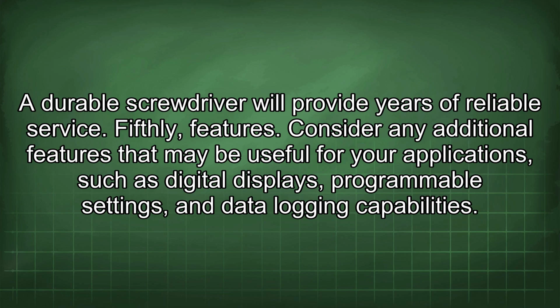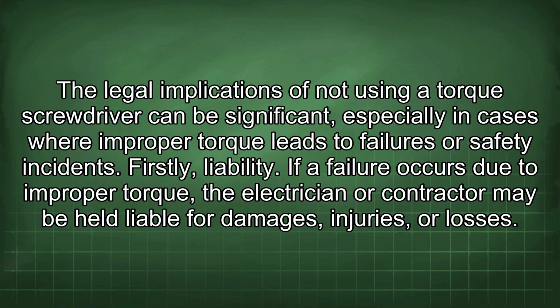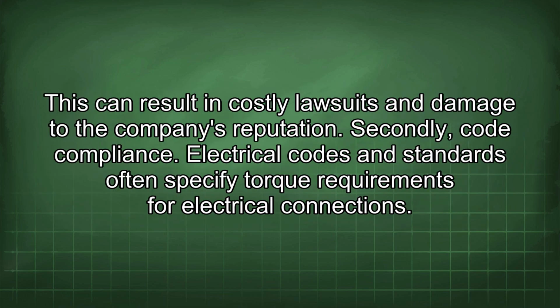data logging capabilities. The legal implications of not using a torque screwdriver can be significant, especially in cases where improper torque leads to failures or safety incidents. Firstly, liability. If a failure occurs due to improper torque, the electrician or contractor may be held liable for damages, injuries, or losses. This can result in costly lawsuits and damage to the company's reputation.